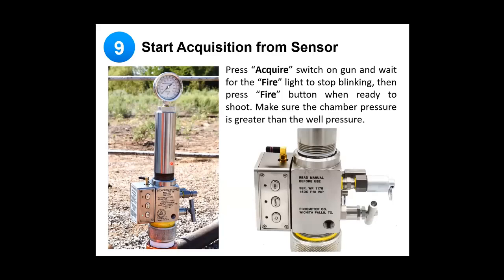One such way is that you can acquire from the sensor itself. As you can see from the images here, we have our power button, which we've made you familiar with. We also have the acquire button and the fire button. We've already selected the liquid level module, and by simply clicking on the acquire button, it will make it so that the microphone is listening to the wellbore. Okay. Now, once the acquire button stops blinking and you have a solid green light next to the fire button, you can push the fire button and fire the shot from the sensor without ever having to walk back to the computer.